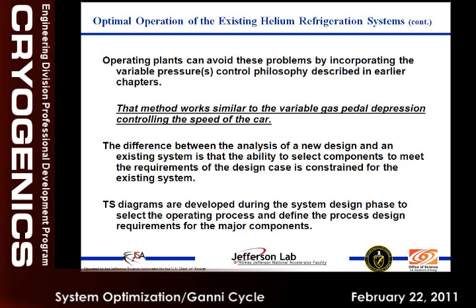By coming up with this adjustable charge, you can take that constraint away. Now, basically, adjustable charge is your gas pedal. That's how you're adjusting the gas, whether in the helium system or in your car. The more gas you give, the pressure will rise. It will produce more capacity, like your car will go at a higher speed. So that's basically what this floating pressure will give you, that you're able to adjust the charge to meet your needs.